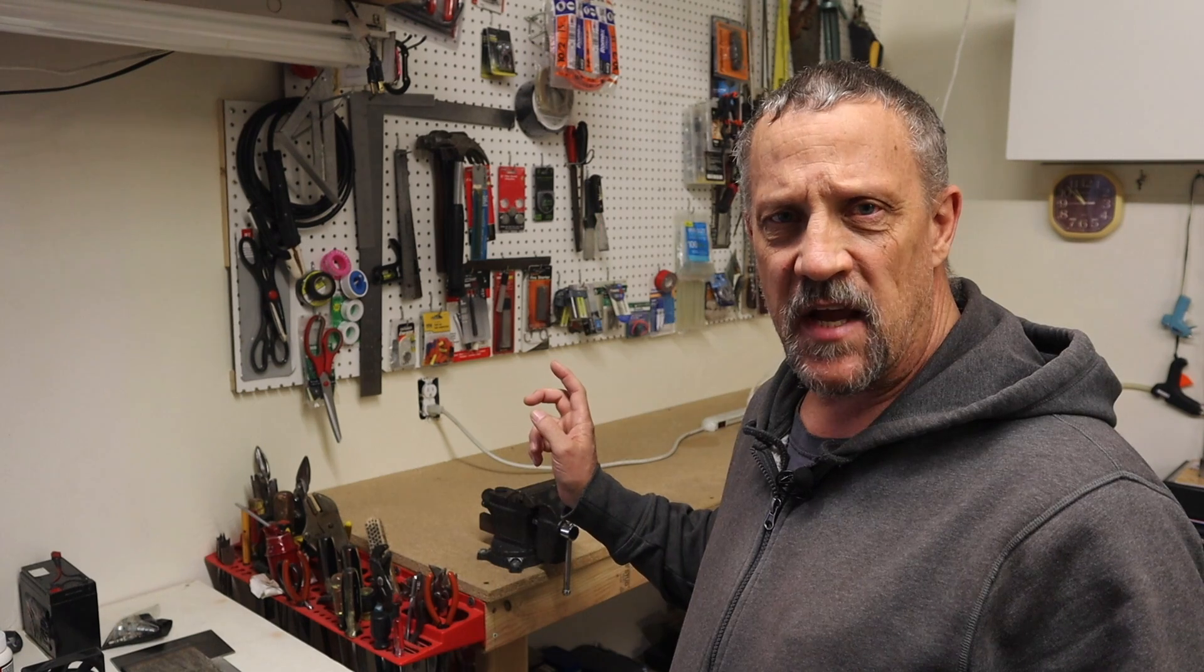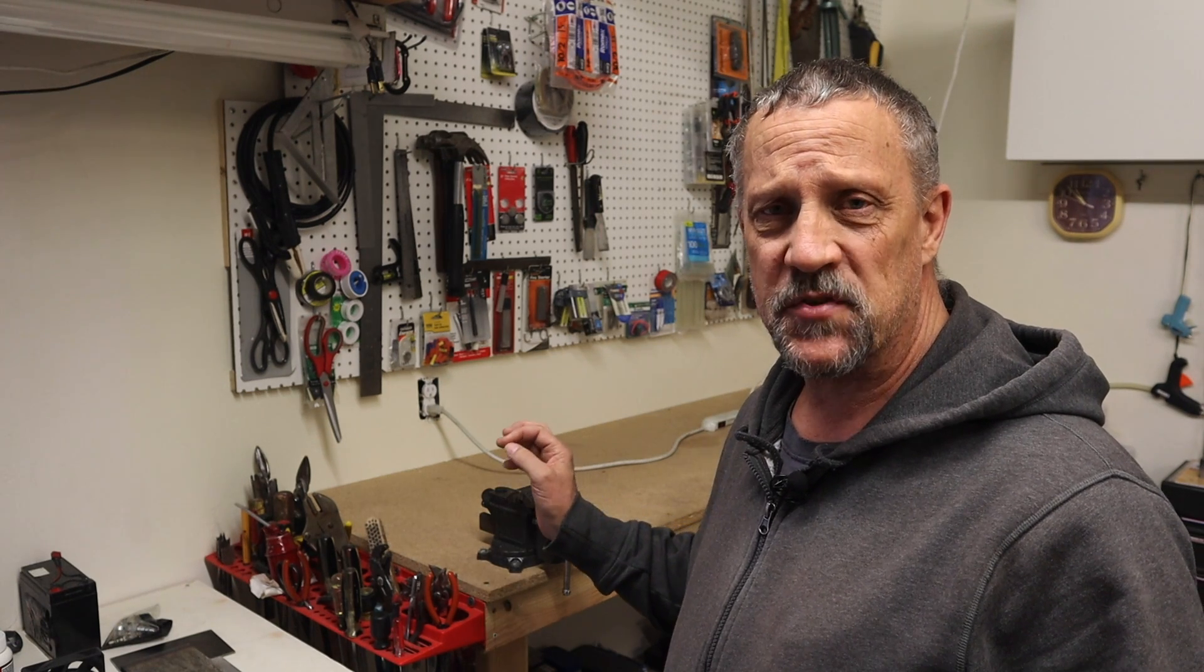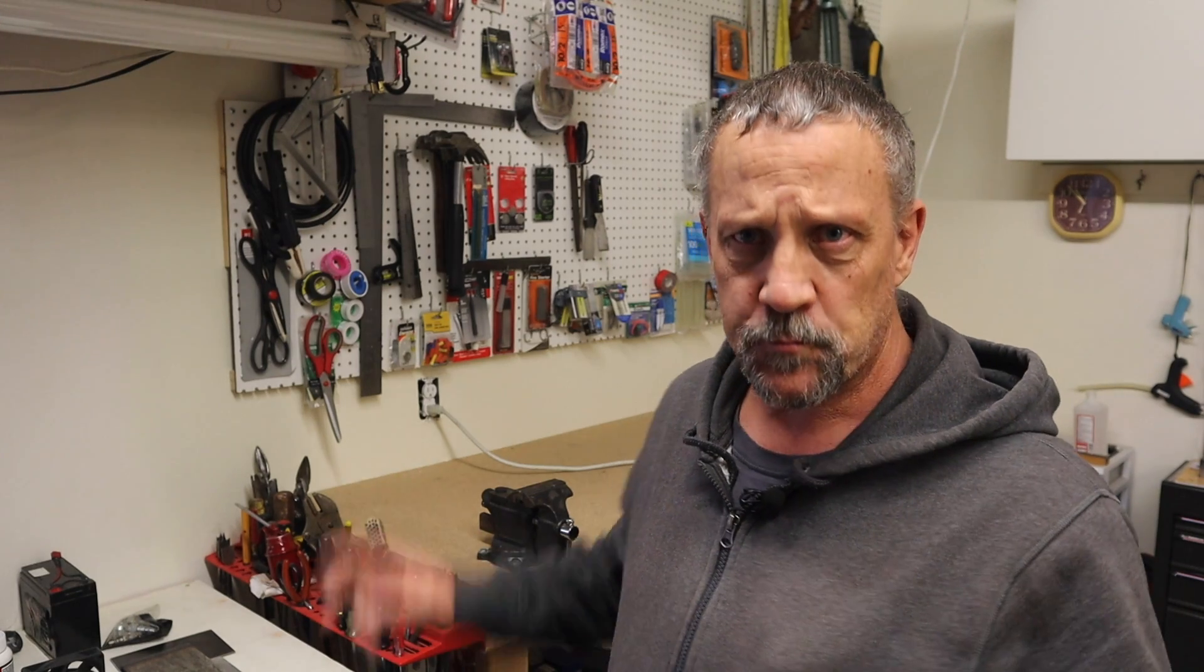This is a typical two-car garage and as a lot of garages come these days, they don't have very many outlets. My particular garage happens to have two outlets and one GFI outlet. That is a 15 amp outlet on a 20 amp circuit. On the other wall is another outlet which is a GFI, also 15 amp. Those two outlets are on the same circuit and this one is downline from the GFI. The builder installed 15 amp outlets on a 20 amp circuit.